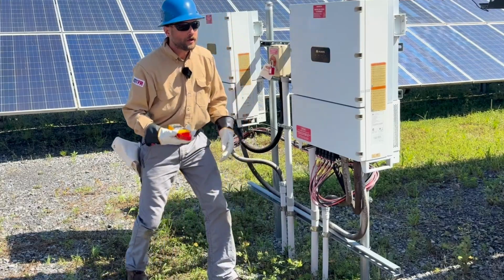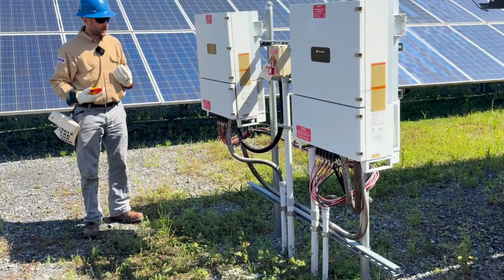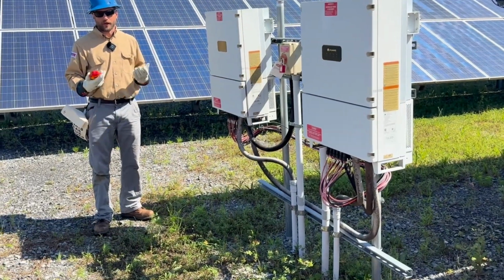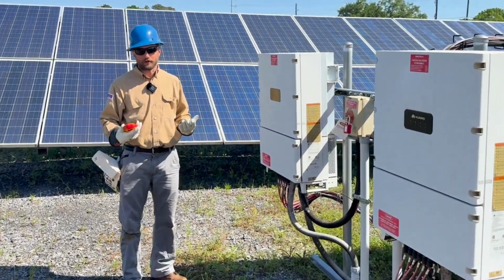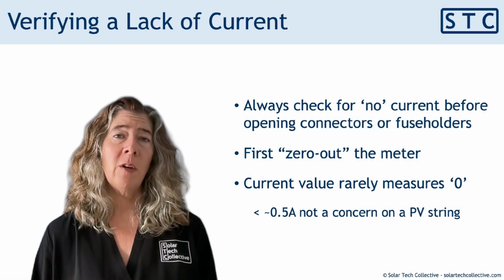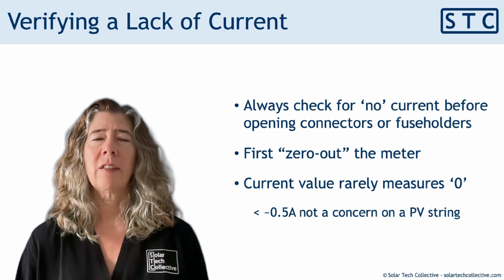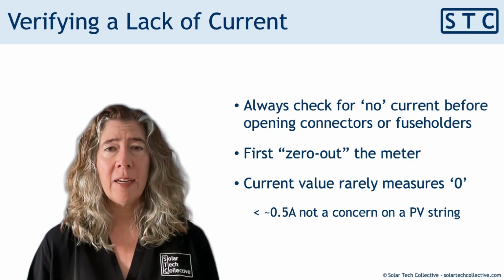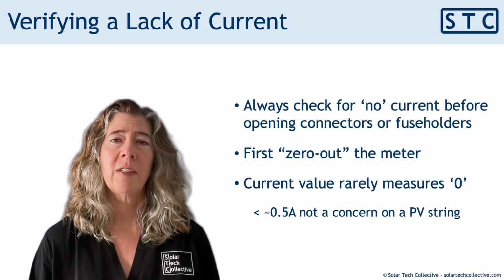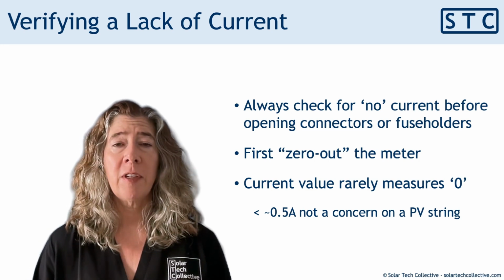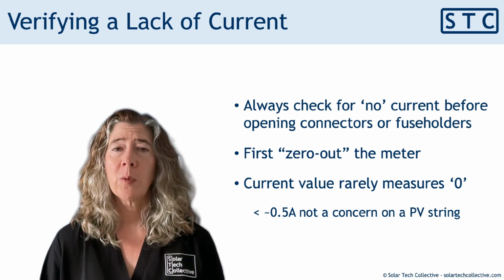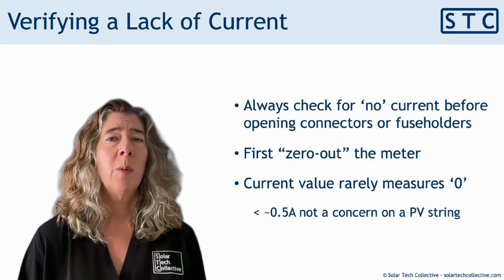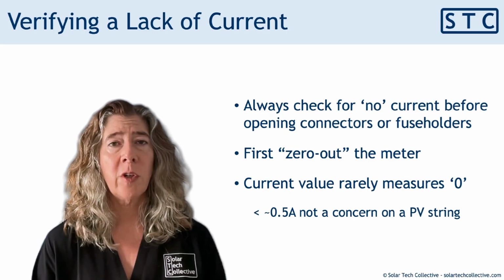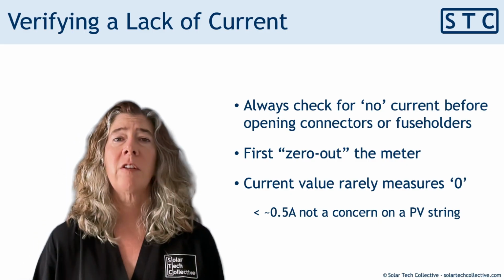Meter's working well. So let's move back to our inverter that has an issue and start testing there to make sure that we have no current present before we disconnect anything. Now that you know your meter's working correctly, what do you do next? Well, before you open any connector or fuse holder on a site, you have to check every single circuit for current. You always want to make sure there's no current flowing before you open a connector or a fuse holder. You don't want to let that arc out. That can start a fire.